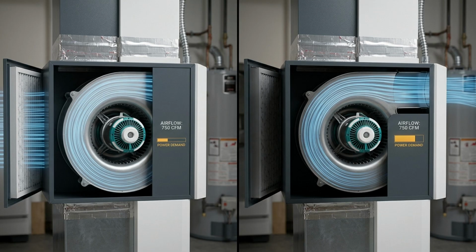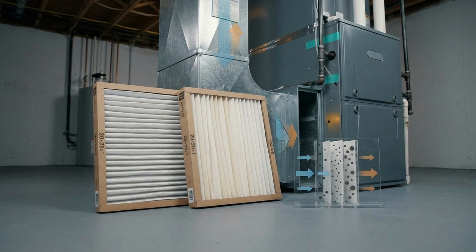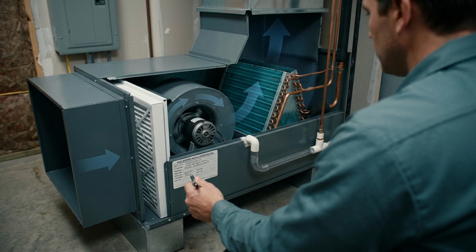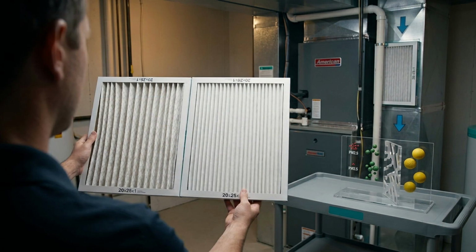These observations are clues. A hand at a vent, a fluttering tissue, or a phone video cannot measure system airflow or total external static pressure. Consider two filters that are both labeled MERV 13 and fit the same nominal opening. One is a thin 1-inch design with limited media area. The other is a deep pleated design and a cabinet built for it. The shared MERV number does not make their pressure drop identical.